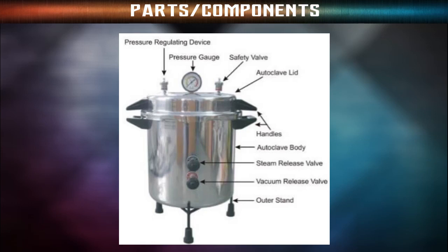Next, coming to the lid and door. The next important component of an autoclave is the lid or door of the autoclave. The purpose of the lid is to seal off the outside atmosphere and create a sterilized condition of heat inside of the autoclave. The lid is made airtight via the screw clamps and asbestos washer. The lid consists of various other components like the pressure gauge.